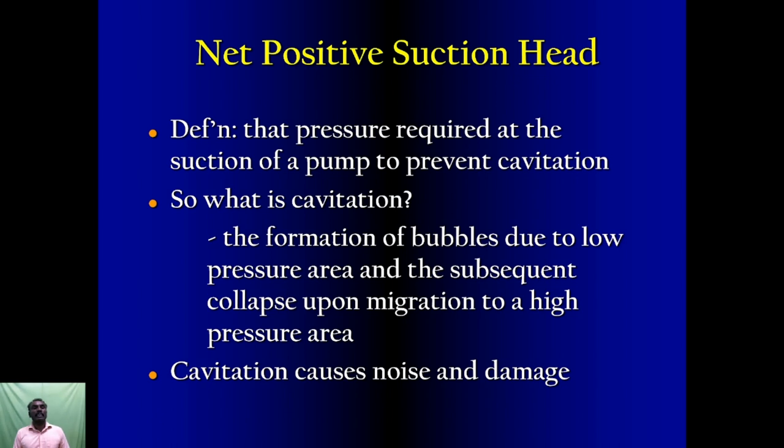Net positive suction head. Definition: the pressure required at the suction of a pump to prevent cavitation. So what is cavitation? The formation of bubbles due to low pressure area and the subsequent collapse upon migration to a higher pressure area.